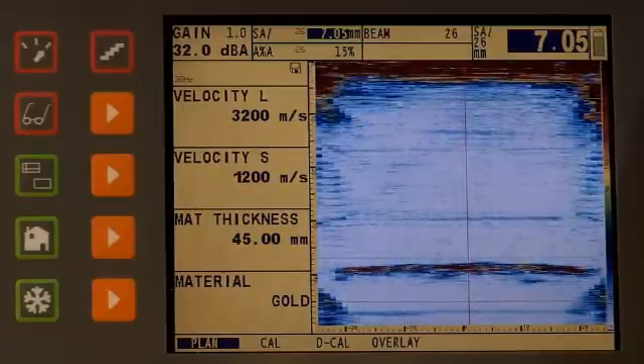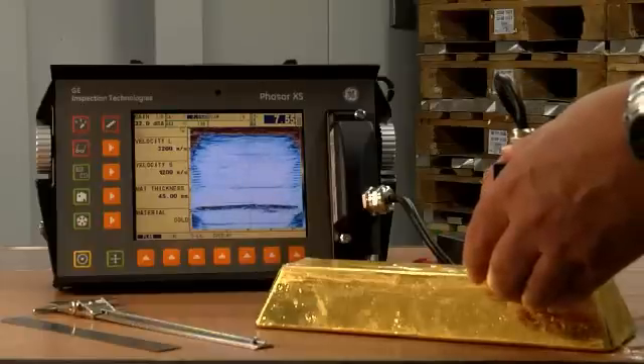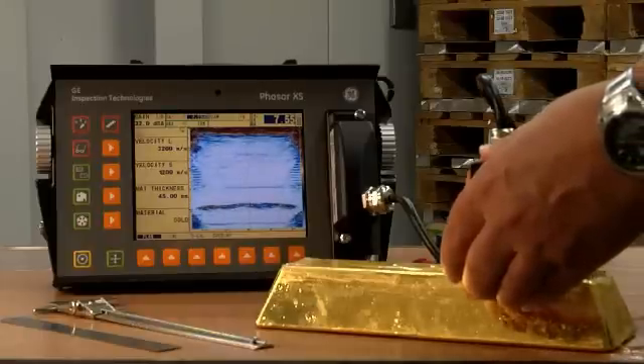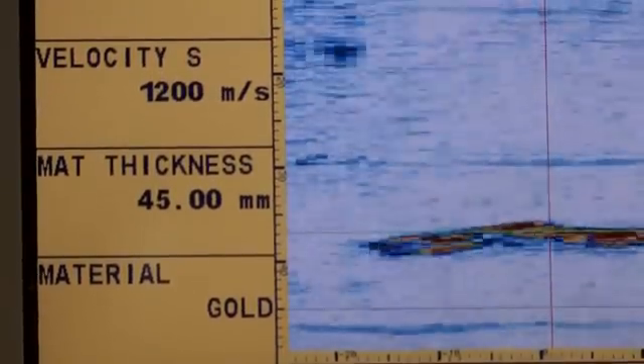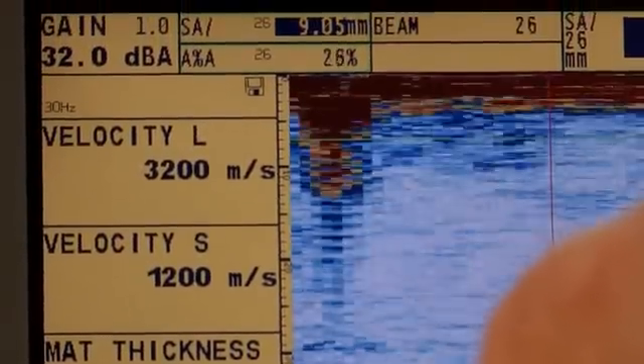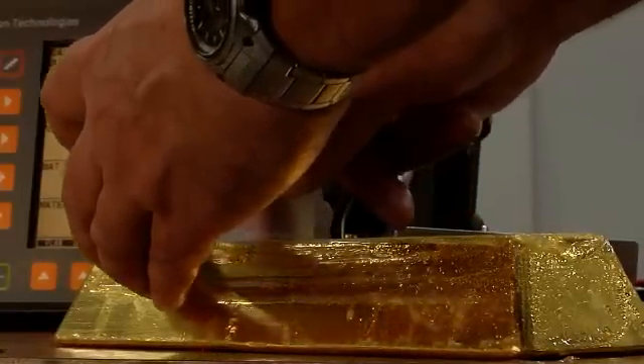So we've got a cross-sectional view and as we move the probe we're effectively non-destructively looking inside the gold bar wherever we position the probe. If we had an air gap, a void, another material inserted in there, the image on the screen would clearly display that.